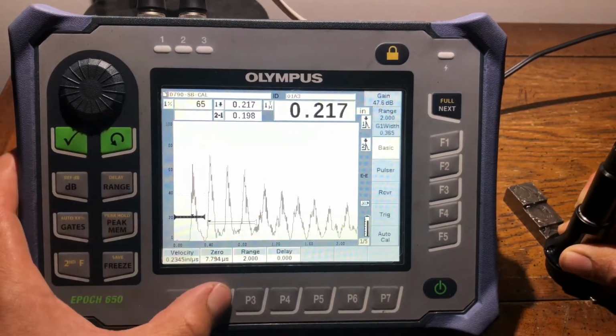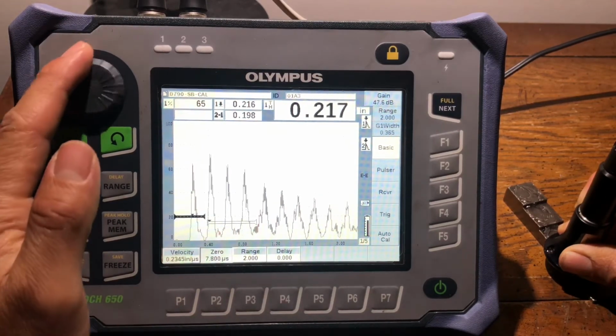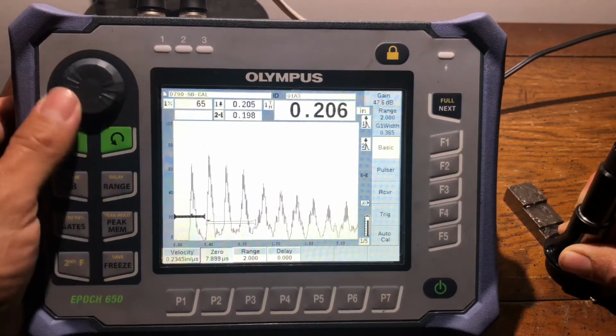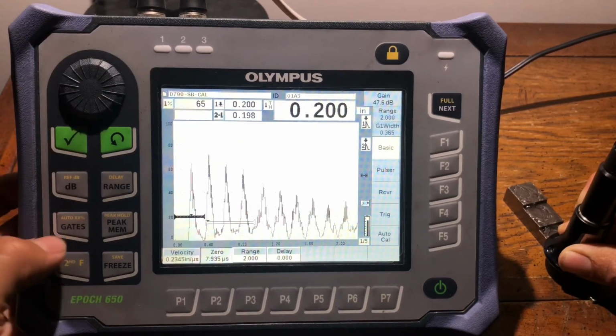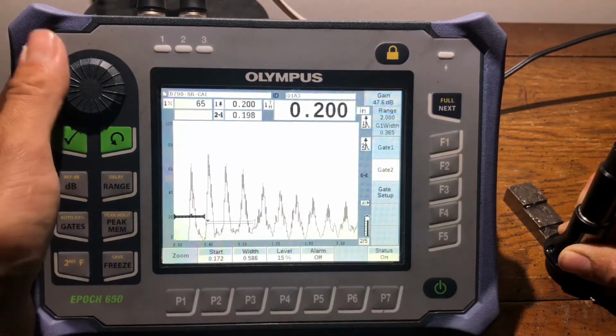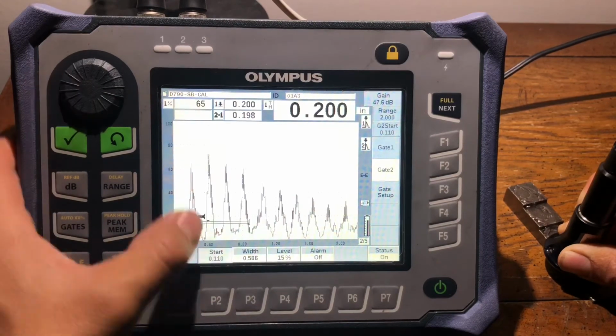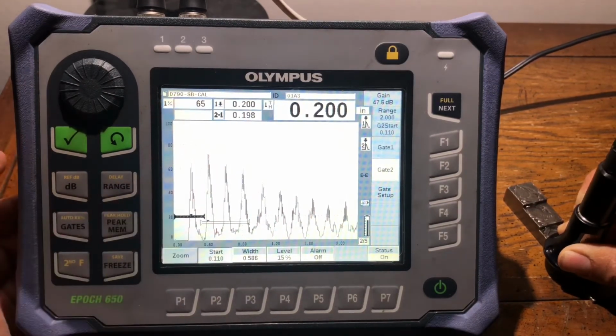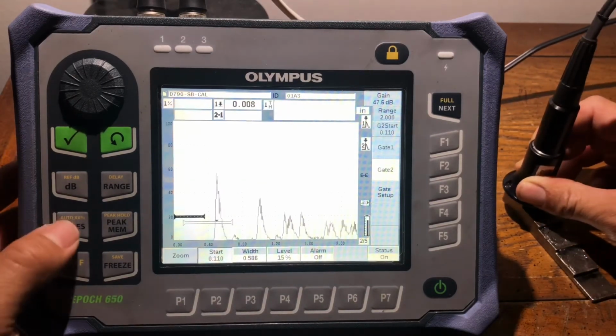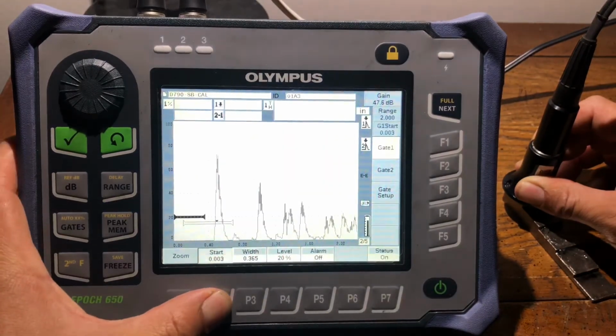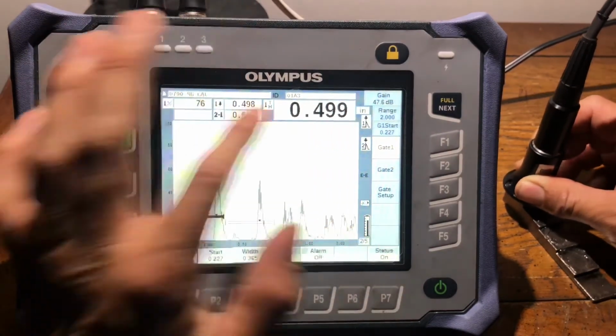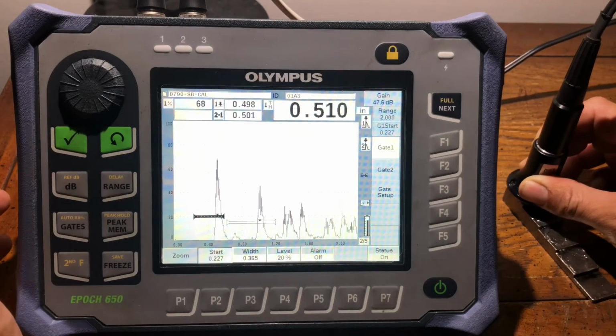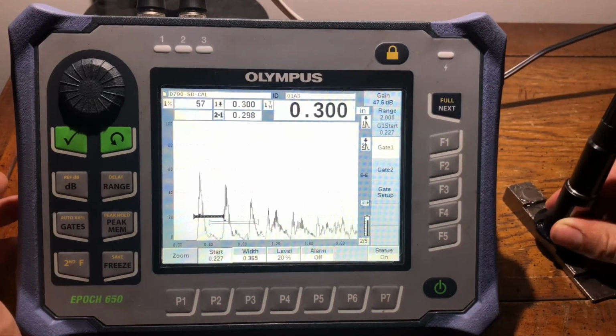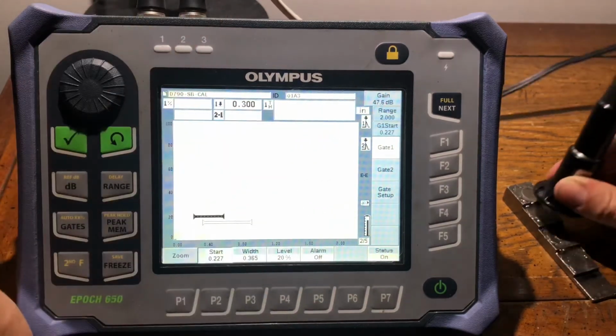So our calibration is a little off, especially right there where our thickness is, but we could just calibrate that really quick. I'm gonna go there, move my 0, and align it to where it should be, which is right about there. I'm gonna go to gate, and move my second gate closer to where it's right in the center. As you can see, we're reading the highest peaks. Now I'm gonna go to the 5 just to make sure that I'm good. I'm gonna go to gate 1, start, and move this, and as you can see, pretty close to being calibrated. This will fluctuate, because this is a dual element, so it'll give me different settings, but pretty much it's pretty good. So as you can see, we're about right, 3 to 3, 4 to 4.